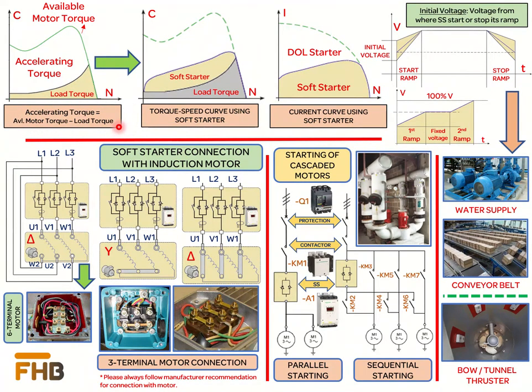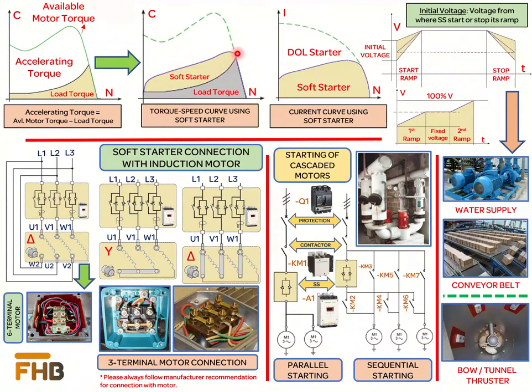As compared to the DOL starter, the soft starter can limit the starting current of the motor at a desired value. However, it is important to mention that by reducing the current of the motor, the available torque also reduces. Therefore, it is necessary that starting current is only reduced to a point where the motor available torque remains greater than the load torque.